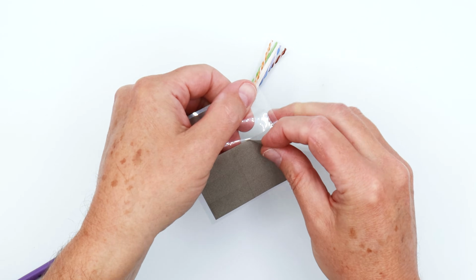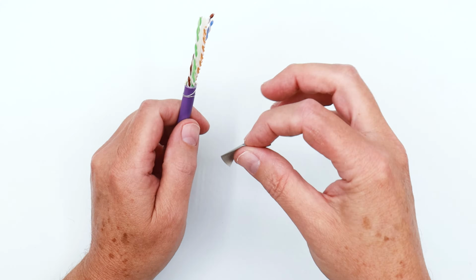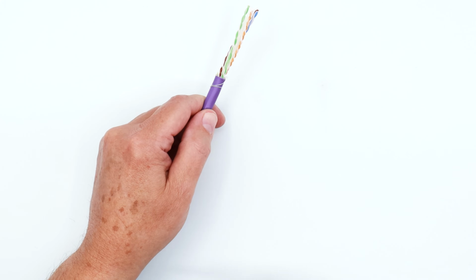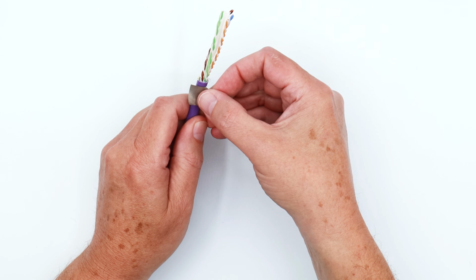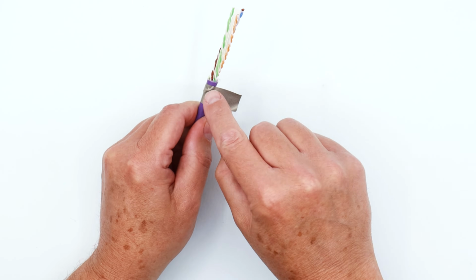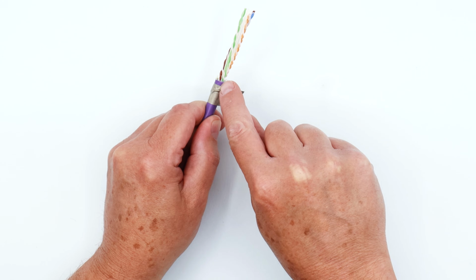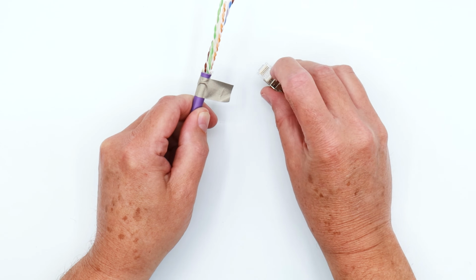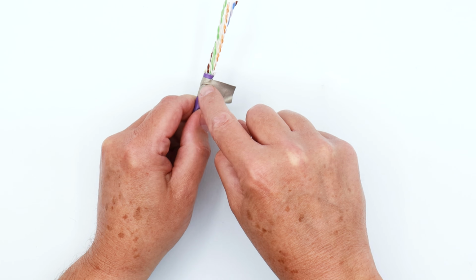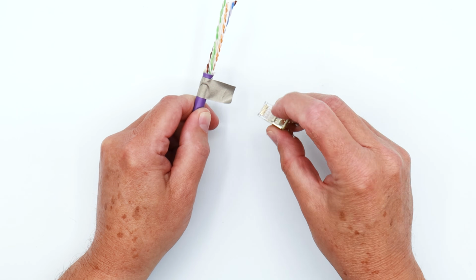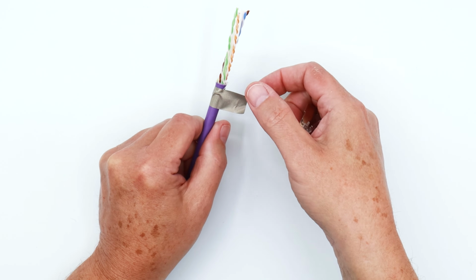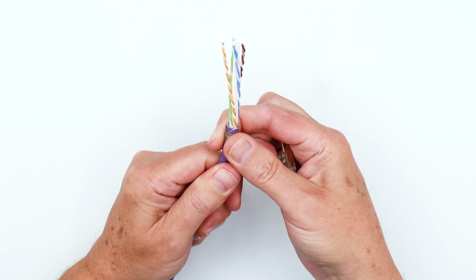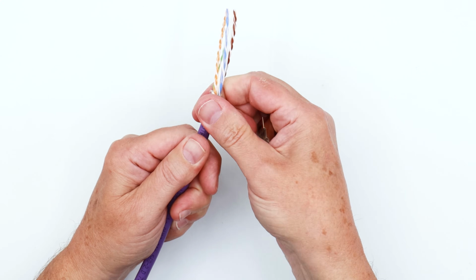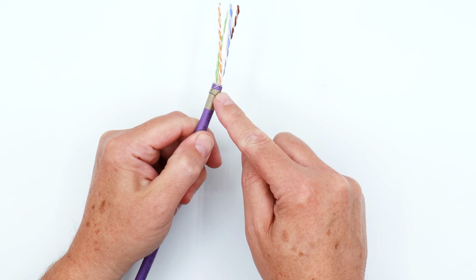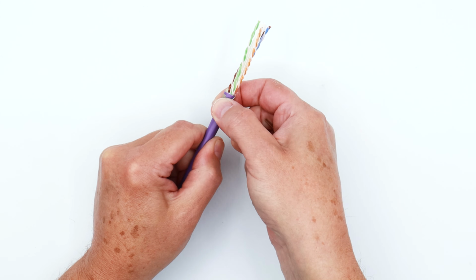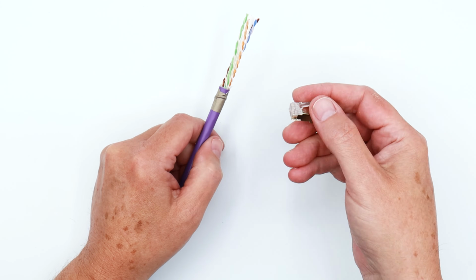So we'll go ahead and take one of those off. And they're very thin. So for this particular plug, I recommend that you skip about an eighth of an inch of the cable jacket and start a little further down. The reason being, you want to be able to see the color of the jacket when you seat it into the plug right here. So if you're seeing just a metallic material, you're kind of seeing metallic here too. It's hard to tell where the cable's stopping at. So skip about an eighth of an inch or so. Pull it on there tight, get it all nice and wrapped. The drain wire is now bonded to this copper fabric strip, which is bonded to the cable shield, which will then bond to your plug.